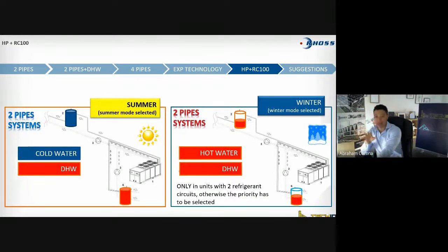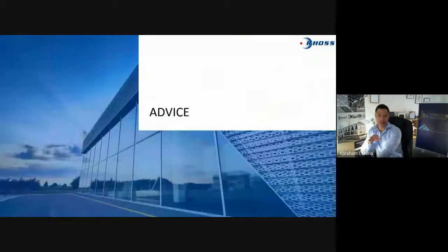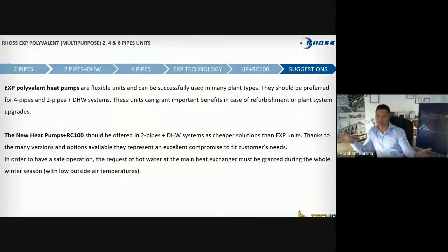So I hope this gives you a bit of an idea of what happens. And if you need a 4-pipe system, please go with a 4-pipe system. This is something we can study case by case. So as advice, it's as simple as that. If you are designing a 4-pipe system, meaning simultaneous cooling and heating, or independent cooling or heating, you need a 4-pipe unit. We can evaluate together, we can help you look for a better solution with 2 pipes, with heat recovery, and we can analyze whether it is suitable for your project or not. You may save a lot of money or not, but keep that in mind.